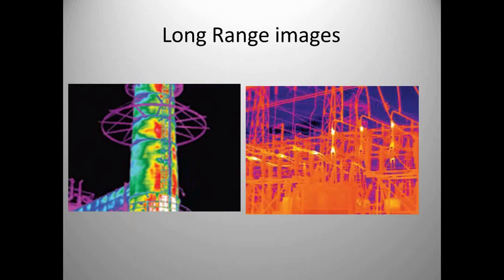Here's an evaporation tower at a refinery — with the camera, easily finding that the insulation is not in good shape on the column. This substation was taken at an Alcoa aluminum foundry outside Montreal. Look at all the loose connections and hot spots in the substation. We also had a substation like this where we found failures — corona, arcing, or tracking — with the ultrasound tool first, then brought thermography in behind it to locate those things and see the intensity. Our first find was with the UE ultrasound tool.